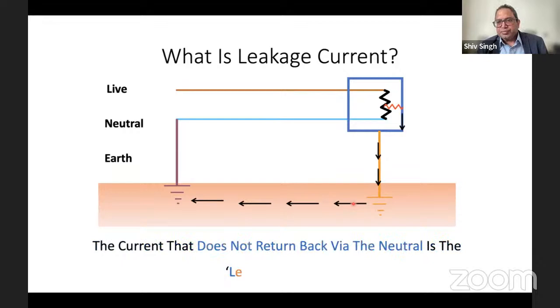And now we know that equipment in the theaters does not actually have an earth wire connected to the body. They do not have a protective earth. That's why it is very, very important that the amount of leakage current is kept to the lowest, that which you do not even feel, or less than 50 microamps, especially in equipment that is connected to the patient. So remember the definition: any current that does not return by the neutral is a leakage current.